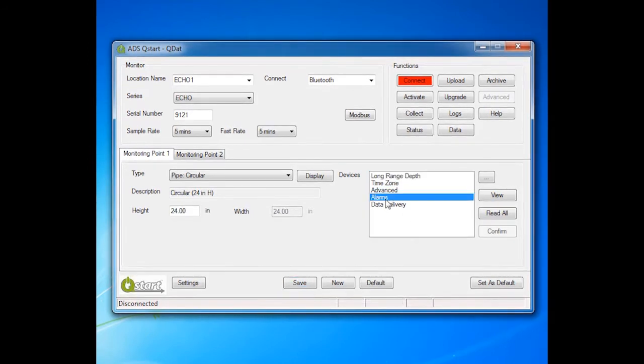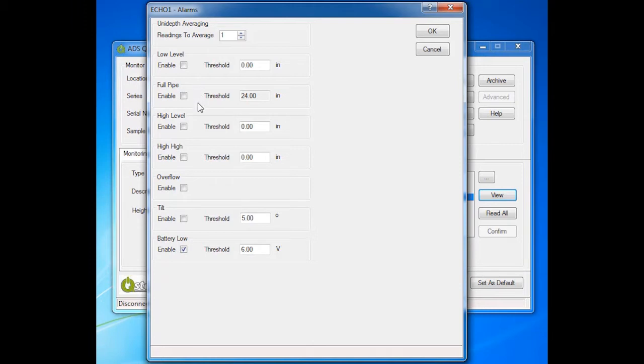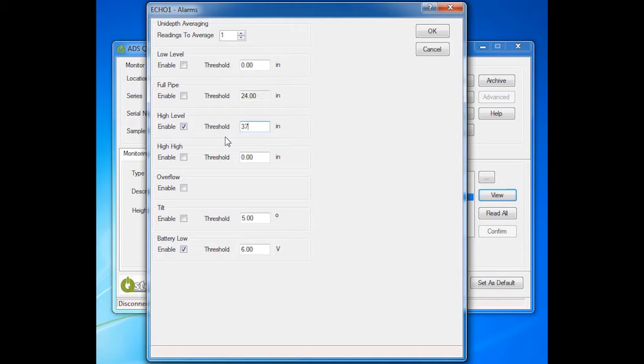Next select Alarms and View to open the Alarms device screen. Configure the alarms of interest. The Echo will trigger an alarm when a threshold is crossed. As an example, check Enable and enter a Depth threshold for High Level. The Echo will trigger a high level alarm when the unidepth value has exceeded the threshold value.